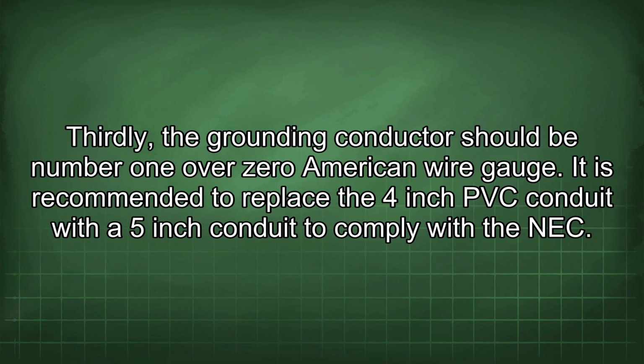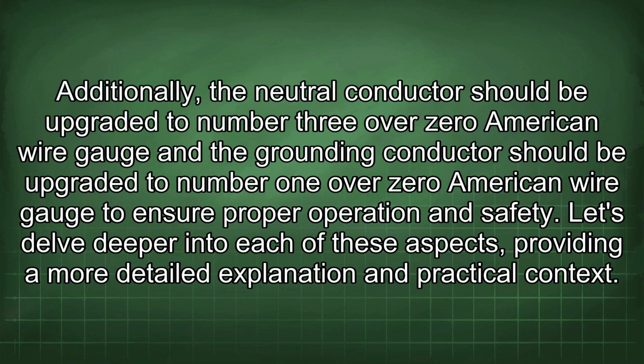It is recommended to replace the 4-inch PVC conduit with a 5-inch conduit to comply with the NEC. Additionally, the neutral conductor should be upgraded to number 3/0 American wire gauge and the grounding conductor should be upgraded to number 1/0 American wire gauge to ensure proper operation and safety. Let's delve deeper into each of these aspects, providing a more detailed explanation and practical context.